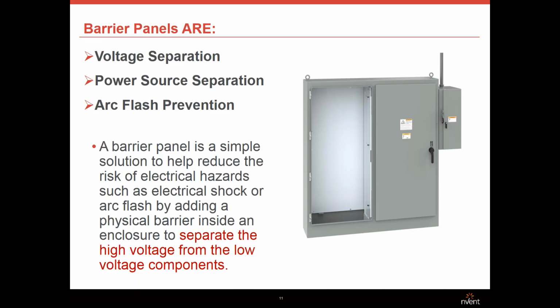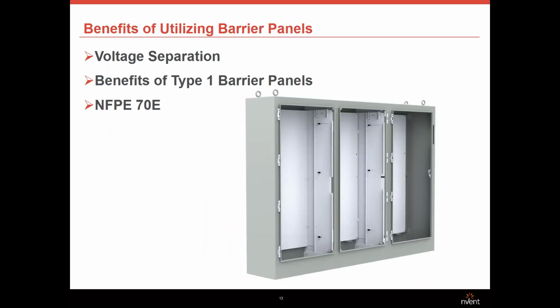So what barrier panels are is voltage separation, power source separation, and arc flash prevention. It's a simple solution to help reduce the risk of electrical hazards, such as electric shock or arc flash, by adding that physical barrier inside the enclosure, oftentimes used to separate high voltage and low voltage compartments. But in the case of power source separation, if you had multiple bays and you had power coming into say the bay on the far left and the bay on the far right, you could have different power sources coming in utilizing some kind of a through-the-door circuit breaker or through-the-door fuse holder that would allow you to have power in different bays of the enclosure.